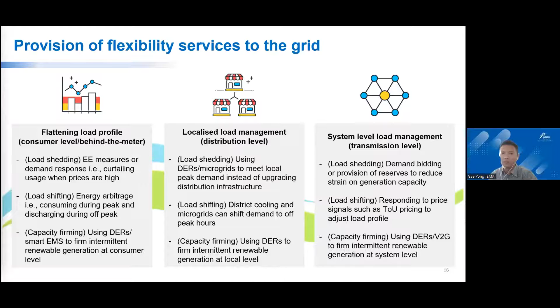So I'll talk through three specific solutions that Singapore is exploring. The first is localized peak shaving with energy storage systems, a regulatory sandbox project between the EMA, the Energy Market Authority, and Singapore Power, our local grid operator. This sandbox is meant to test the usefulness of energy storage systems in shaving peak loads at the local substation level, potentially reducing the requirement to install new substation and transformer equipment to meet higher loads.